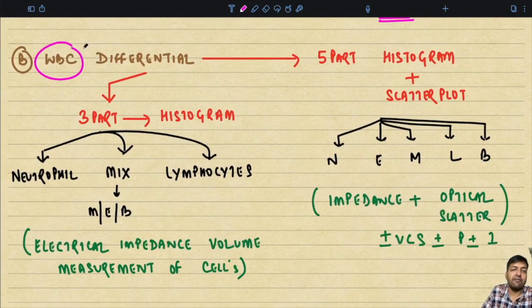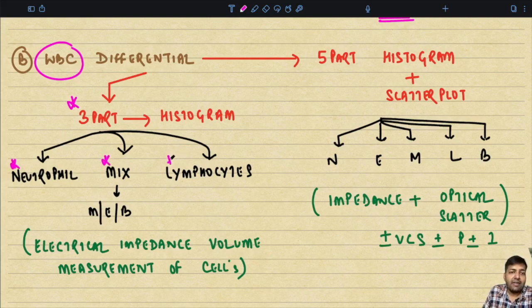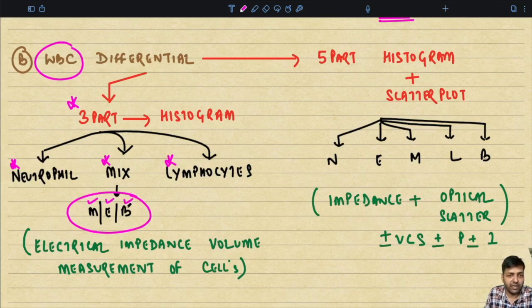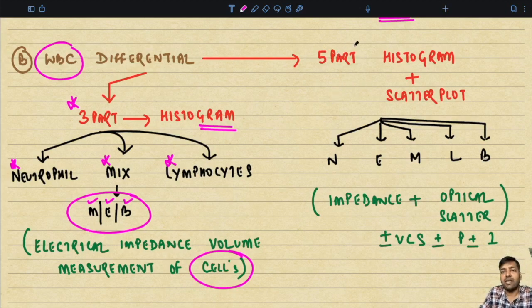The WBC differential can be done in two ways. In the three-part automated analyzers, the three-part differentiates WBCs into neutrophils, a middle mix, and lymphocytes. The middle or mix variety in normal individuals comprises monocytes, eosinophils, and basophils. This is based on electrical impedance-based volume measurement of the cell. The three-part machines also generate histograms: RBC histogram, platelet histogram, and WBC histogram.